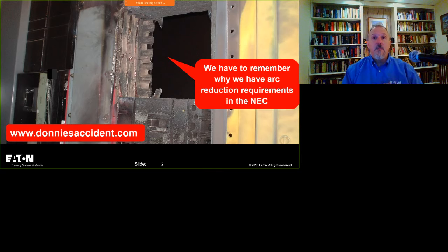Now, 70E tells us that we have to label equipment with an incident energy and working space and things of that nature. And we're supposed to leverage resources and tools. They reference in 70E IEEE 1584, the Ralph Lee method, and the Doan method for DC. So there are various methods to calculate incident energy. IEEE 1584 is a document made by engineers, by IEEE. It was based on a consortium of people who pitched in money. They ran tests in a lab over and over to come up with equations, and those equations are used to calculate incident energy and arcing currents and things of that nature.